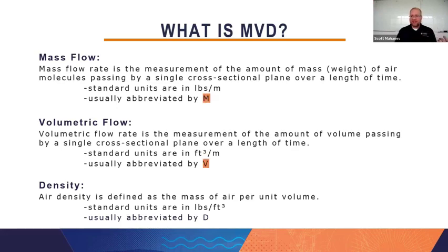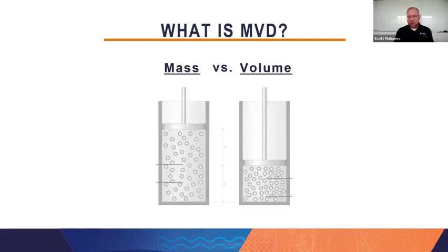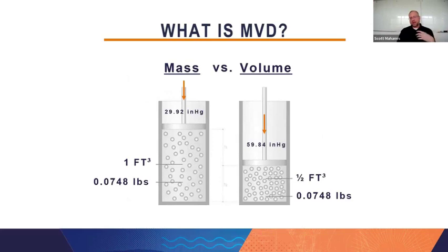So here's a new way of thinking about MVD: mass, volume, and density. I have a pretty interesting illustration that shows the difference between mass and volume. If you had a container with 1 cubic foot of air trapped inside, at basically standard density conditions, the mass of that air could be 0.0748 pounds, about 0.075 pounds. If I add pressure to this container and reduce the volume by half, the volume has changed by half, but what doesn't change at all is the mass.